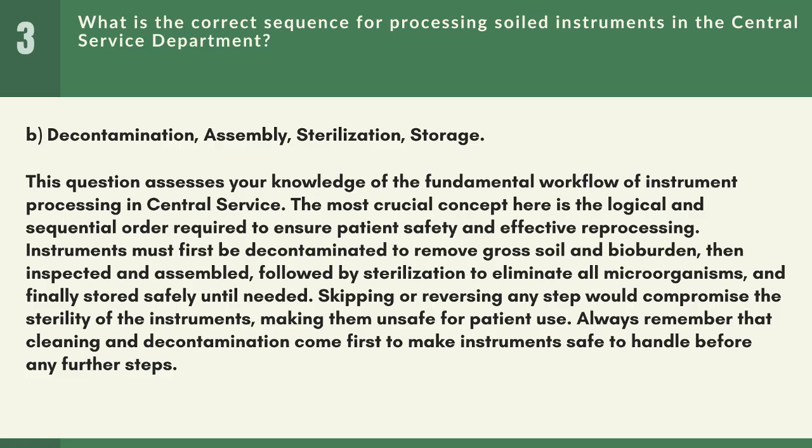Instruments must first be decontaminated to remove gross soil and bioburden, then inspected and assembled, followed by sterilization to eliminate all microorganisms, and finally stored safely until needed. Skipping or reversing any step would compromise the sterility of the instruments, making them unsafe for patient use. Always remember that cleaning and decontamination come first to make instruments safe to handle before any further steps.